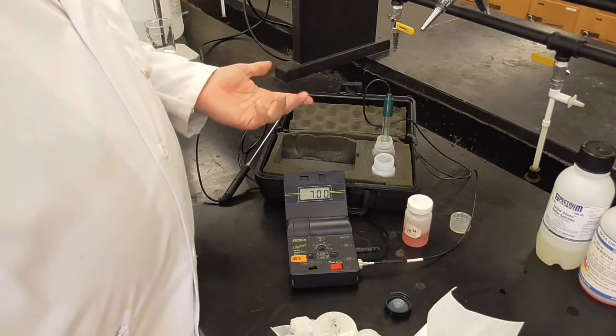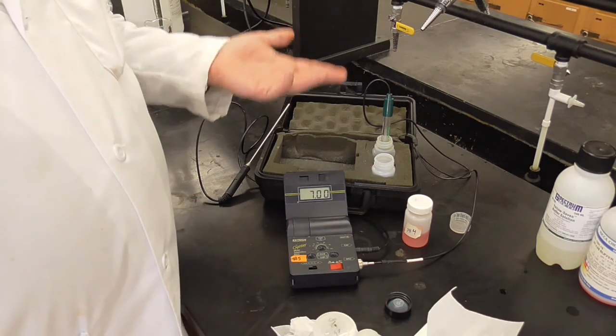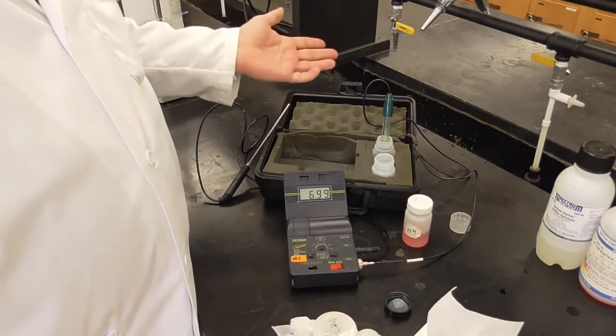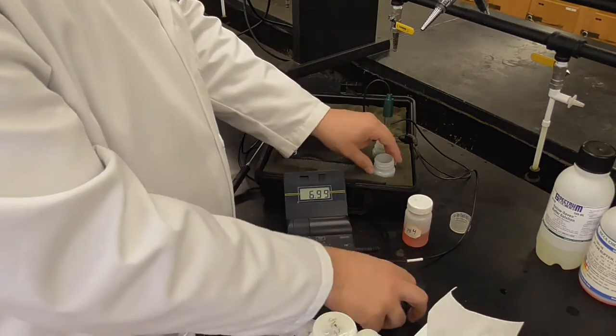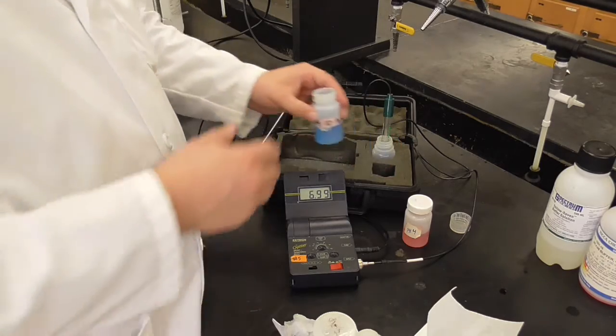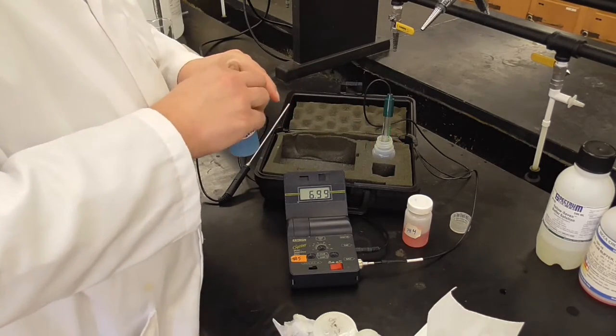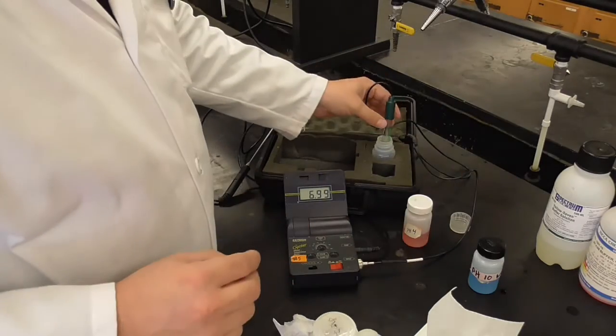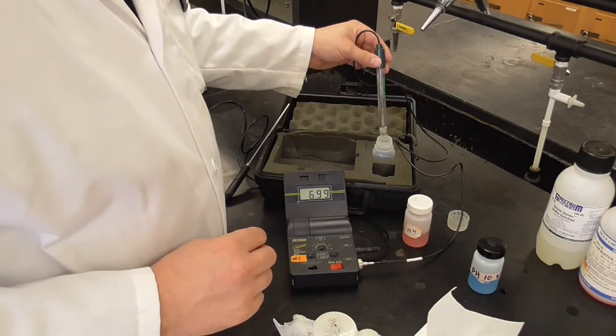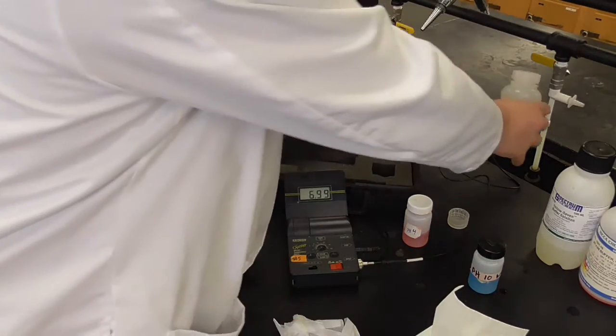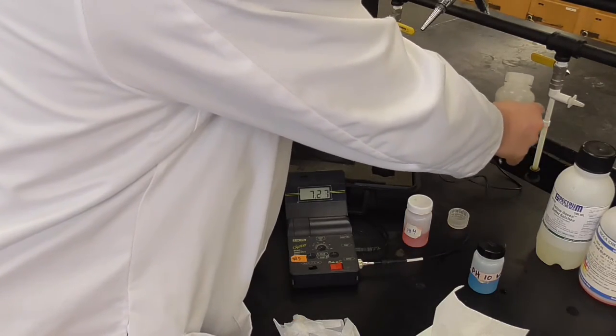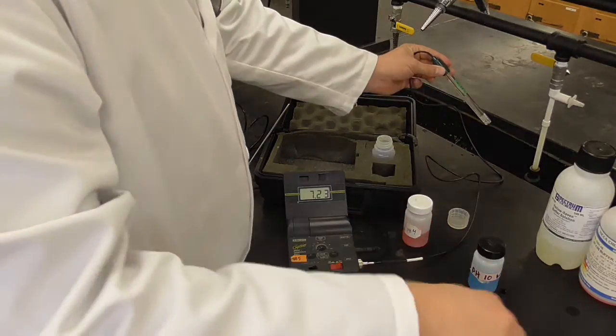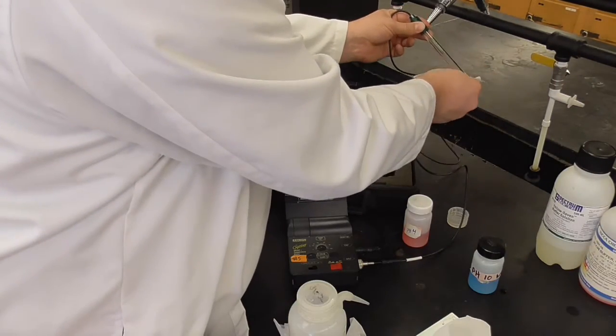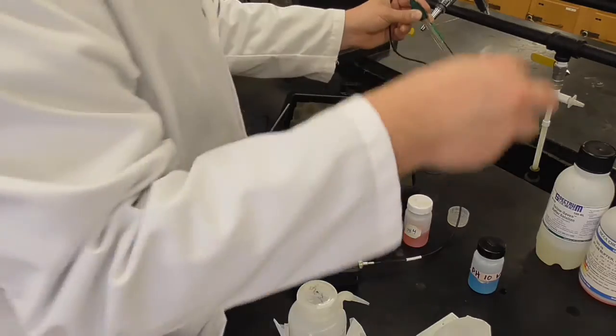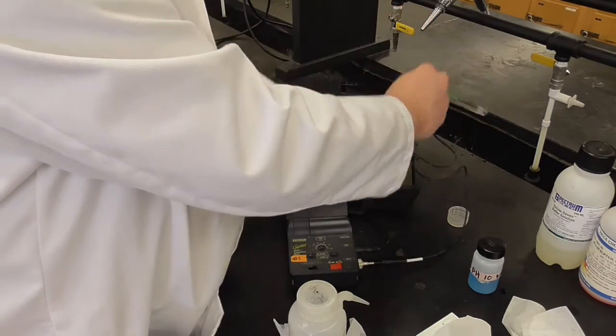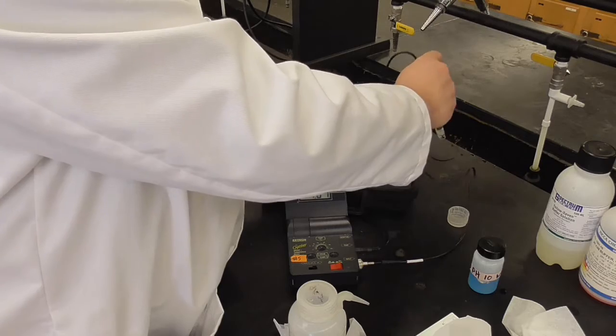Okay, so it's calibrated. Now, just to check to see how good the calibration is, and this you wouldn't have to do, I'm going to go ahead and rinse it and put it in the pH 4 buffer, and let's see how good it goes that way, just as a test. Okay, so again, rinse this off. Dab it dry. Now I'm going to put it into the pH 4 buffer, just to see where that would be.